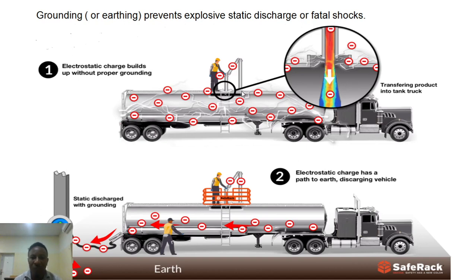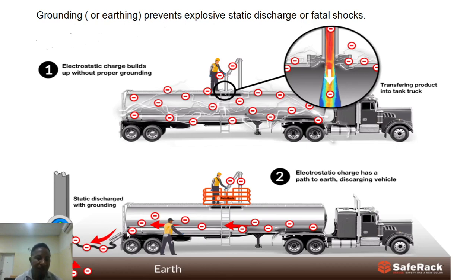If there is a sudden discharge of this negative charge in any way, there could be a fire outbreak or explosion because fuel is highly flammable. But a way to prevent this hazard is simply by connecting any metallic part of the tanker to the earth using a conducting wire, so that is a safe path for electrons to flow to the earth, leaving the tanker neutral with net charge zero.